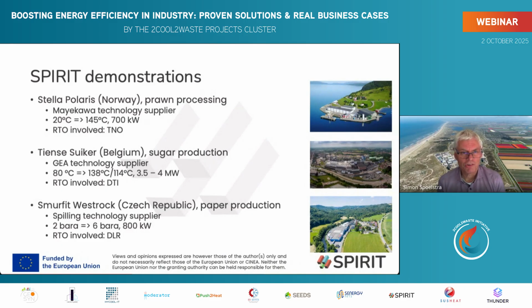The second demonstration is in Belgium, at a sugar mill. Here, GEA supplied a heat pump using waste heat from a multi-stage evaporator. The last stage has vacuum steam which cannot be used again, so that heat is upgraded to temperatures of about 110 to 140 degrees by the GEA heat pump, which also uses pentane as a working medium. The size here is about 3.5 to 4 megawatts.